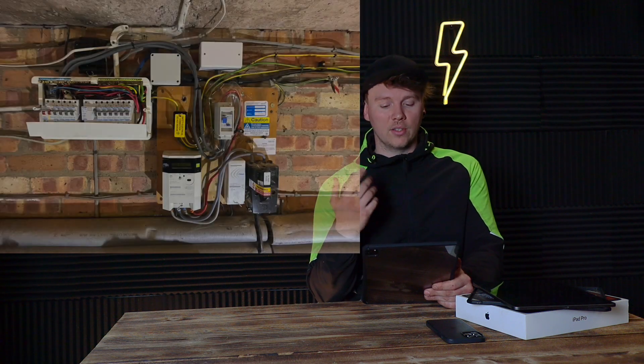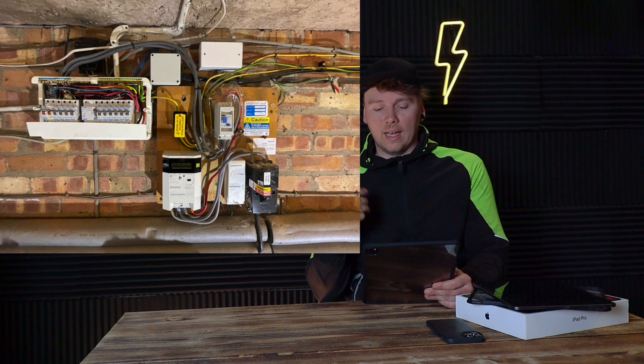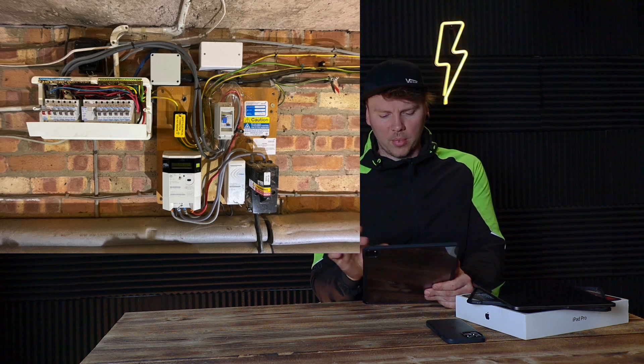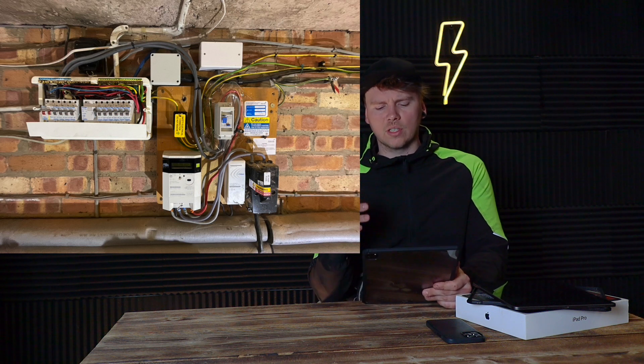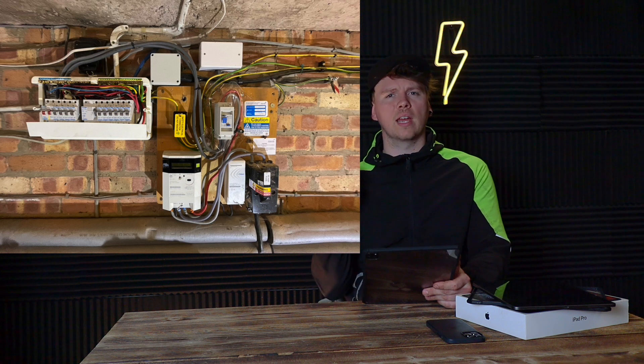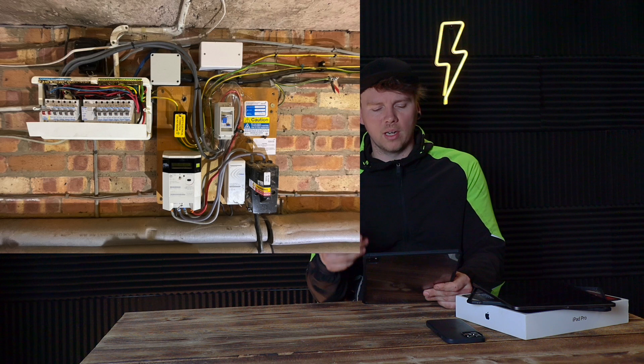Now we're on to pictures I took in the course of literally two days of doing EICRs. This very first picture was just a callout for power tripping. We turned up and the fuse board lid was missing — hadn't been on for years. The DNO had been out and put a cover over the top of the RCD. I'm guessing it was a TT system because there's a 100 milliamp RCD for a main switch. The DNO have recently started screwing plastic covers over the cables at entry points — I presume it's to deal with single insulated cables instead of having to change them, creating a barrier.